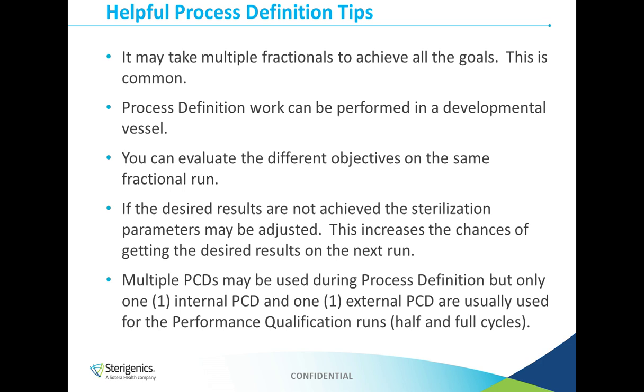If you do go with a developmental chamber, ISO 11135 does have some requirements, such as you have to have an IQ/OQ performed in that developmental chamber. It's the same thing that you would need for your production vessel. You also have to be able to show that that developmental chamber can produce the same parameters and the same conditions that the production vessel can. You have to remember, you want this to represent your routine process. So if that developmental chamber can't provide the same parameters or the same conditions, you're not really representing what you're going to see during routine processing.